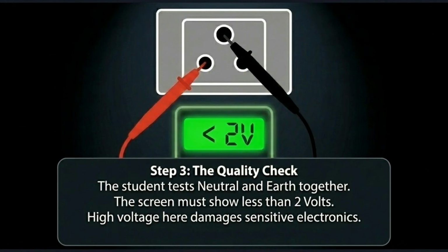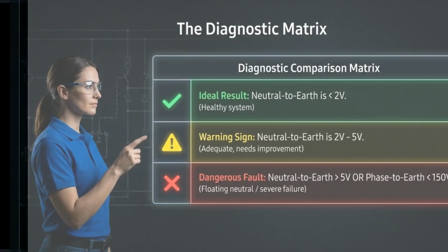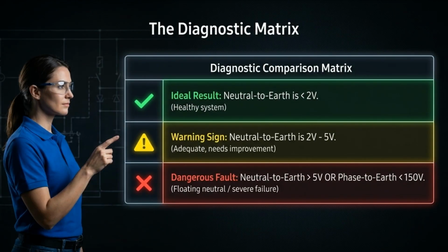Step 3 is the quality check. Test neutral and earth together. The screen must show less than 2 volts. High voltage here can damage sensitive electronics. Use this diagnostic matrix to interpret your results. An ideal result shows neutral to earth is under 2 volts. A dangerous fault is indicated by a reading above 5 volts, or phase to earth under 150 volts.